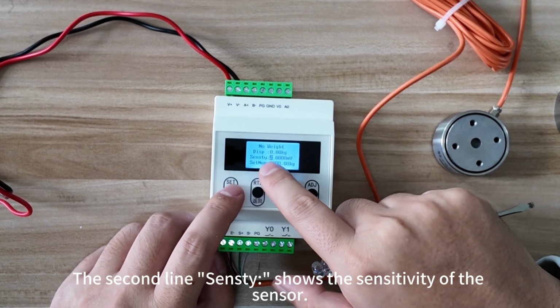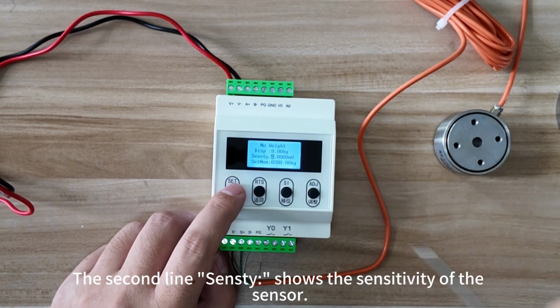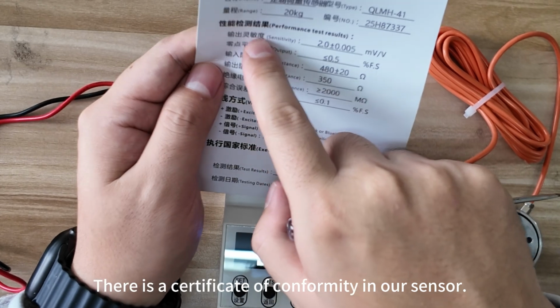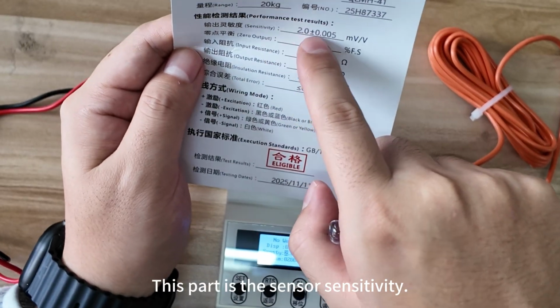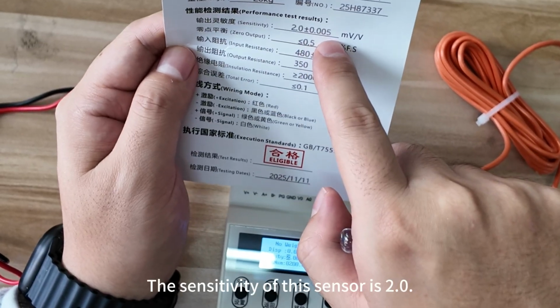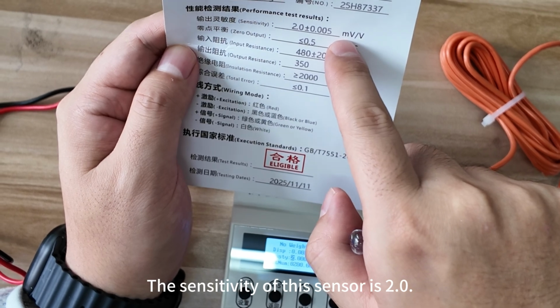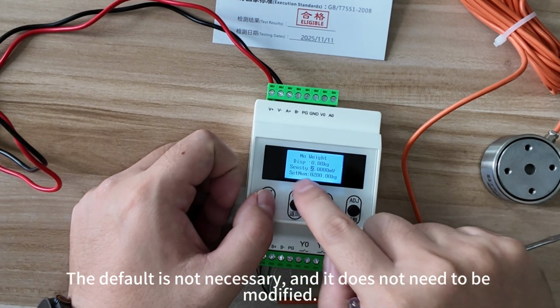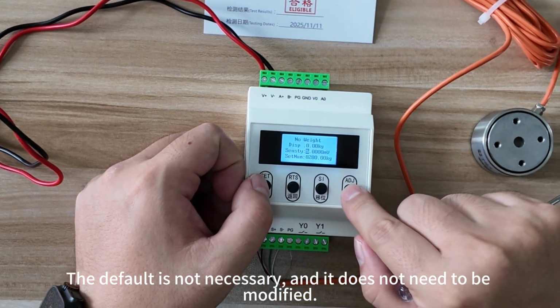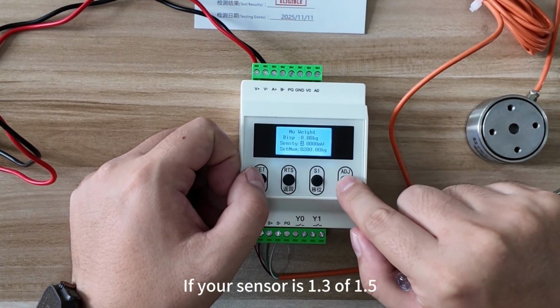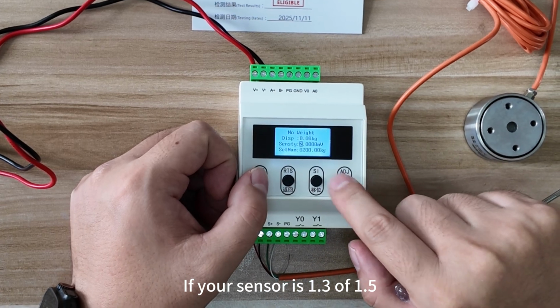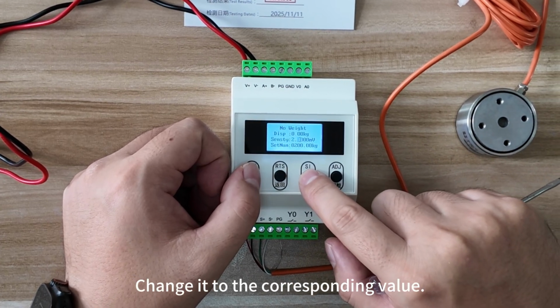The second line, Sensity, shows the sensitivity of the sensor. There is a certificate of conformity in our sensor. This part is the sensor sensitivity. The sensitivity of this sensor is 2.0. Let's change this to 2.0. The default is not necessary, and it does not need to be modified. If your sensor is 1.3 or 1.5, change it to the corresponding value.